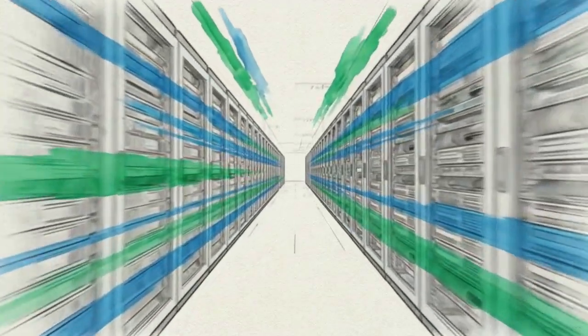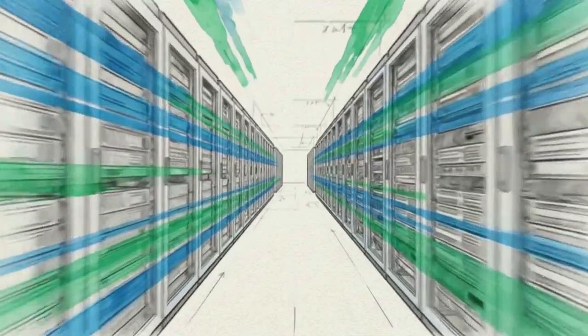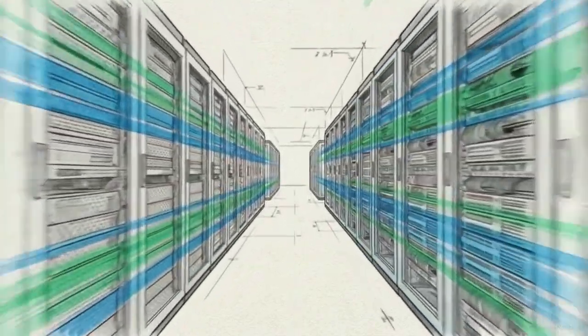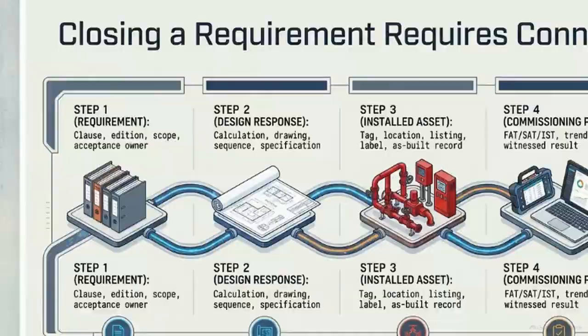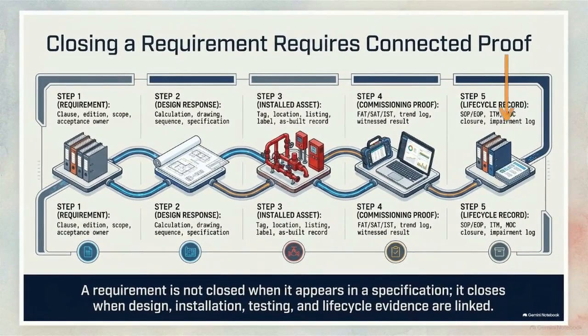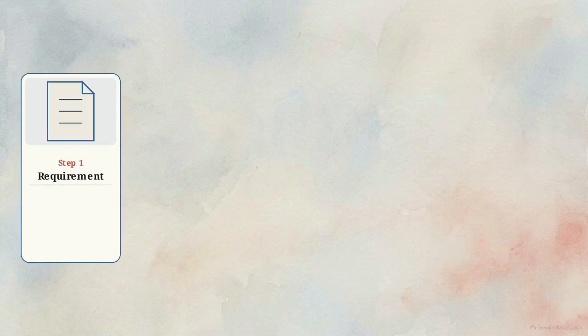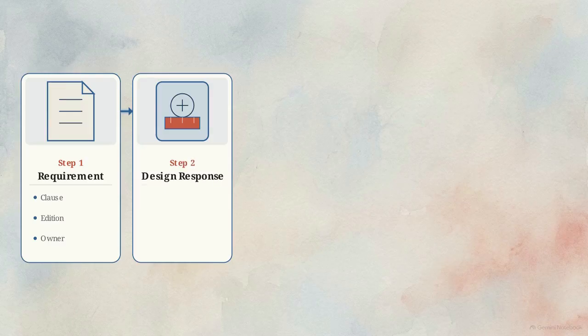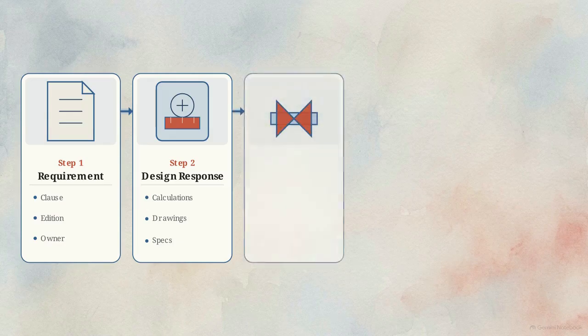Understanding the hierarchy is only the first step. The real challenge is proving those abstract rules actually exist in the physical data hall. This flowchart illustrates why a requirement is not closed just because it appears in a specification. It only becomes real when it is tracked through a rigorous 5-step chain of evidence. First, we isolate a specific clause and its acceptance owner. Then, that clause must generate a concrete design response, a specific calculation, drawing, or cause and effect matrix. That design then becomes a physical installed asset with a specific tag and listing.